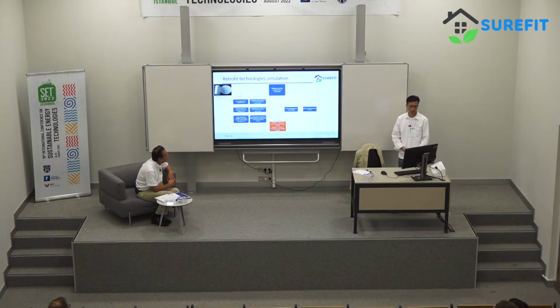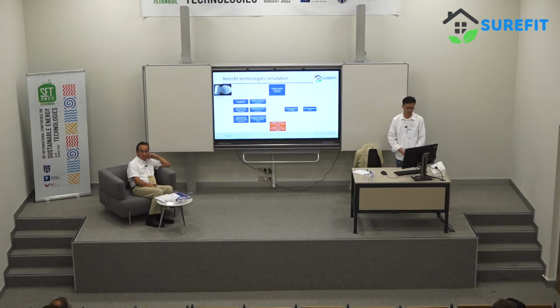In the passive package, the first technology is bioaerogel thermal insulation. It is a thermal insulation material developed by University of Nottingham. It is quite environmental friendly. So it has a significant impact on the U value of the building envelope. For example, before renovation, the external walls is 1.0, and after renovation is 0.4. So in the simulation, we assumed all of the roof and the external wall will be covered by this kind of thermal insulation material.